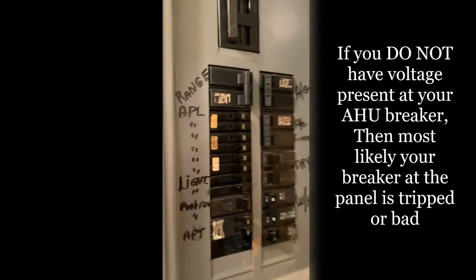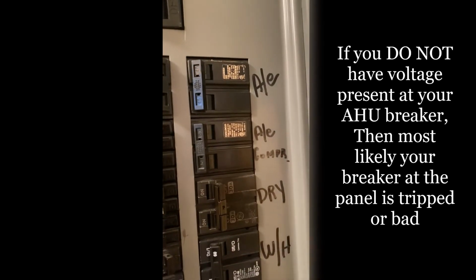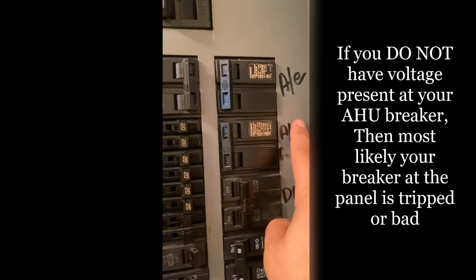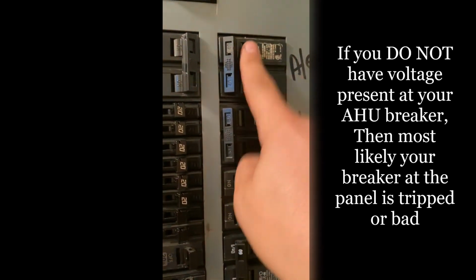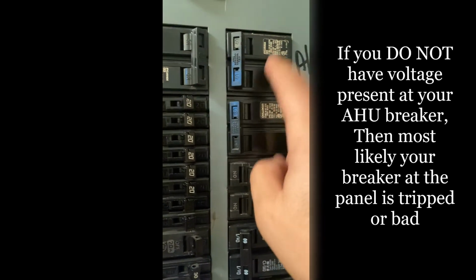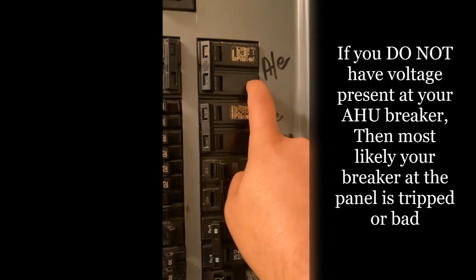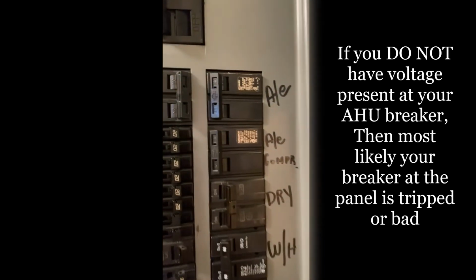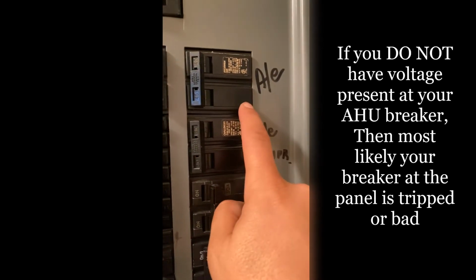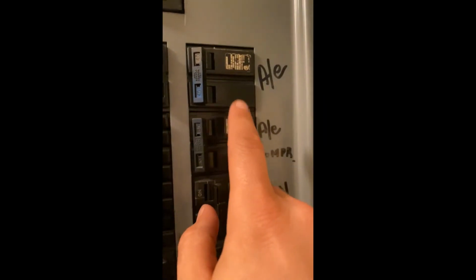All right, labeled. So I've got my air handler, my compressor right here. I have voltage, so it's not tripped. But if you do not have voltage there, most likely it's either tripped or the breaker is bad. If you don't know about breakers, I'll make a video on breakers.